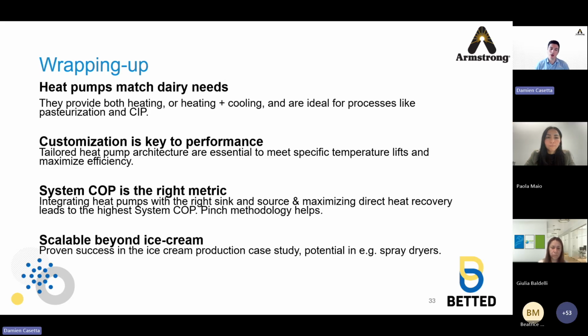If you don't integrate well, then you can get a system COP of 2. And if the difference between gas and electricity is 4, then there is no payback. But if you get it right, use the right methodologies, combine the knowledge from the process, the utility, and the heat pump technology, then you can get system COP above the ratio between gas and electricity, and it's then decreasing the OPEX for the customer.